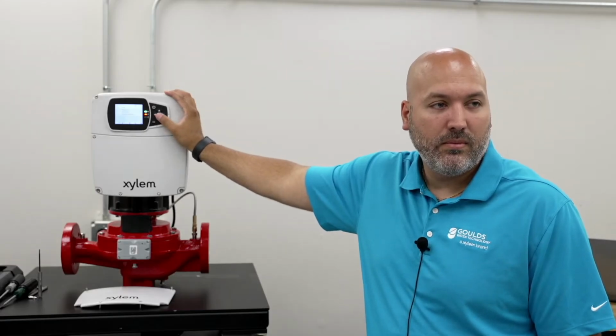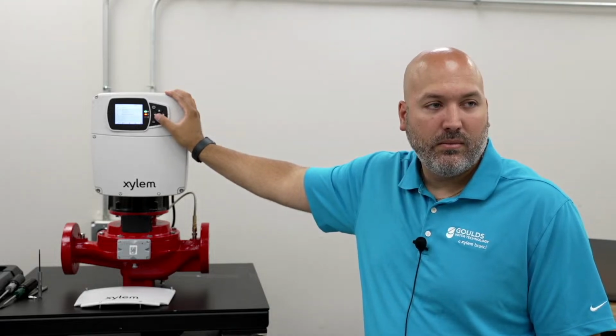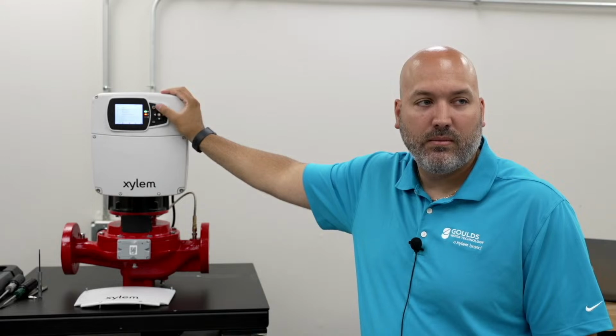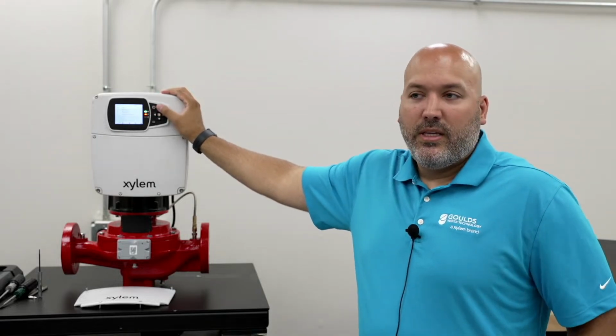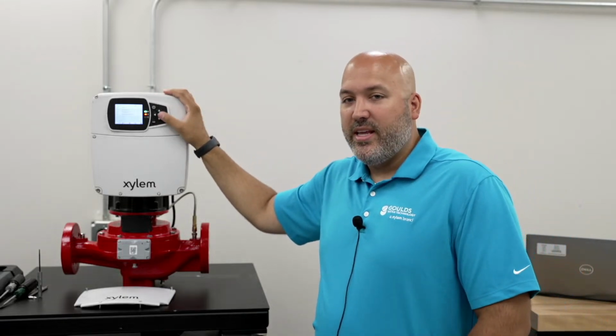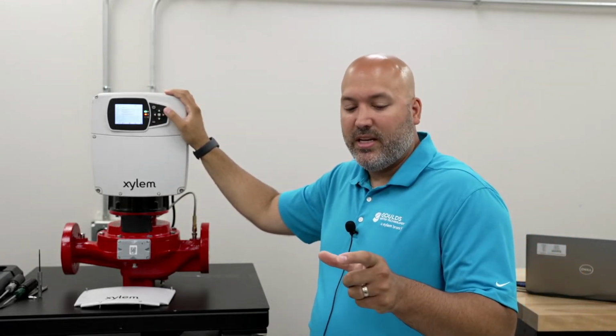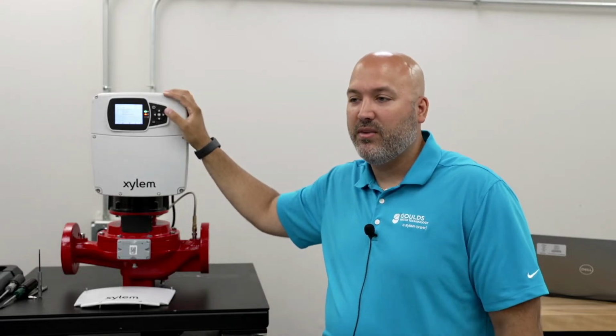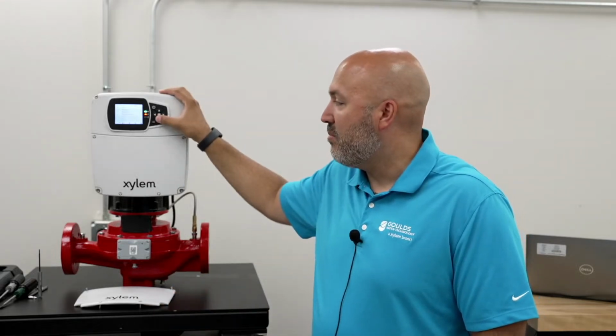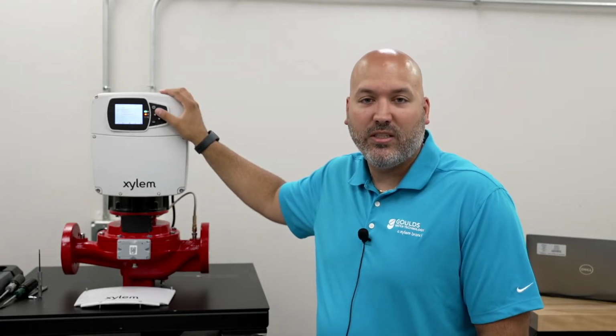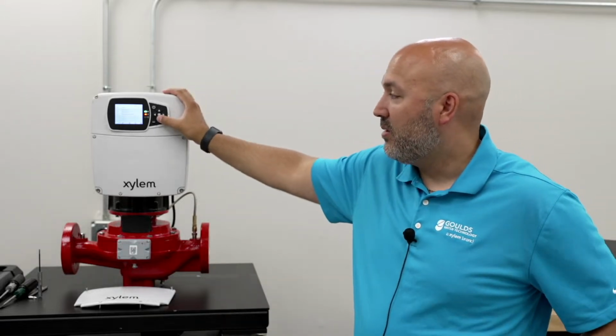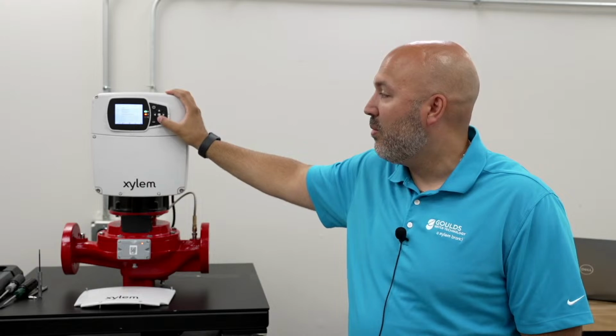Expand a little more on the additional AnyBus protocol, for if you have to tie into a SCADA system where the facility doesn't have the Modbus or BACnet that you mentioned. Yeah, to keep it simple, it's really just a third-party module. AnyBus is the name of the company or the module. They have a bunch of different protocols. In the simplest terms, BACnet MSTP or Modbus RTU is a language, right? That's how the two machines communicate with each other. They need to speak the same language. So if a customer's existing system doesn't have Modbus RTU or BACnet MSTP, we're basically buying a language card so the two units can properly communicate with each other.